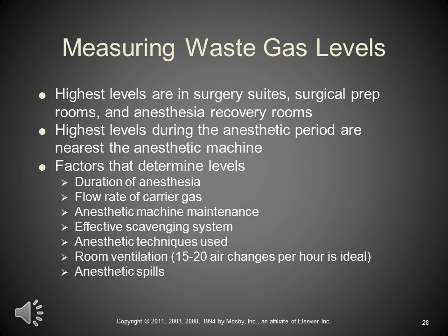Factors that would determine the levels, of course, are how long we go through anesthesia, the duration, the flow rate of the carrier gas. The more oxygen that's going through, the more exposure you're probably going to have to anesthetic gases. Maintenance of the machines, an effective scavenging system, the type of technique being used, room ventilation, and we want 15 to 20 air changes per hour. That would be ideal. And then the presence of any anesthetic spills. Obviously, if you spill a whole bottle of isoflurane or sevoflurane right at your feet, you're going to get a big exposure. If you don't do that, then you won't.